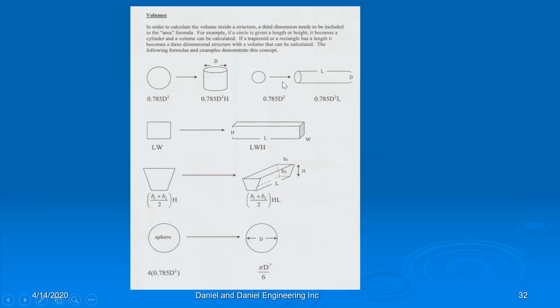And look at it from this point of view. In our pipes, we've been bringing it closer to home, right? We'll have the circle here, a circular pipe, and we talk about a length of pipe. Based on this length of pipe, we realize a cylinder is being formed. So we could calculate the volume of water at X distance away. There's a circular pipe, and then we're talking about a length, right? So we're talking about a volume of 0.785, the diameter squared, times the length.